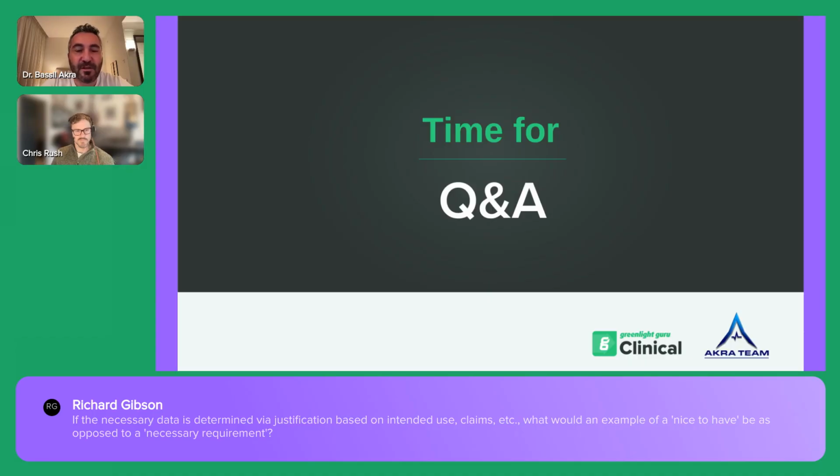So for example, if you have a sterile wrap and you say, I could justify safety and performance with non-clinical data, and then you say, I'm going to be sending a questionnaire to the user to ask them about their satisfaction with my device. This is customer feedback, which is not actually necessary for PMCF activity.